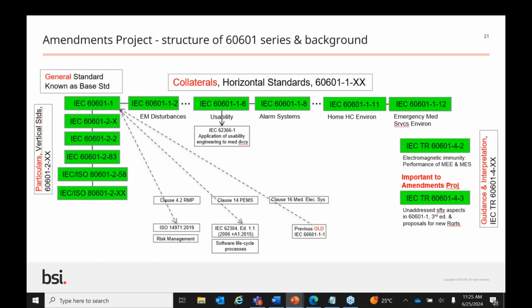So as Holly sort of talked about the layout, here's a picture that gives you a little more layout. This is the layout of the current 601 series. So in the upper left-hand corner, you have the general standard, and across the top, you have the collaterals, the -1s. Down the left side are the particulars, or sometimes called the vertical standards. On the right, you have the TRs, the technical reports, the -4s, which are disappearing at this point and mostly turning into technical specifications because of changes in the rules with IEC and ISO. For the fourth edition, the collaterals will actually get compressed into the general standard. So the structure is going to look a little different, to be determined a little bit. Next slide, please.